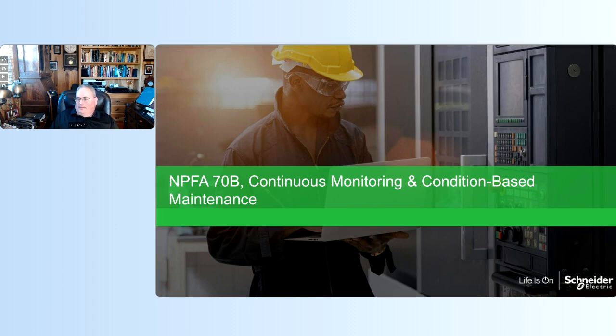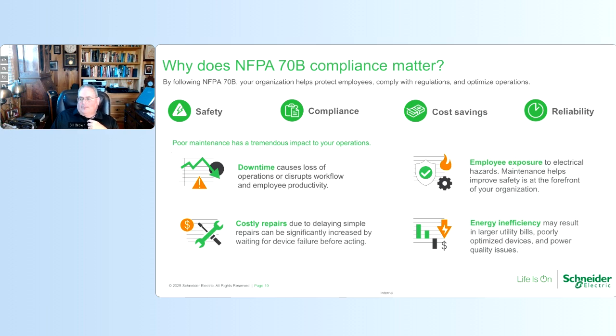So now we're going to talk a little bit about condition-based maintenance in NFPA 70B. So why does NFPA 70B compliance matter? Well, in 2024, NFPA 70B took on the status of an NFPA standard as opposed to a guide. And it can be used by OSHA in citations. While it isn't adopted by governmental jurisdictions the way the National Electrical Code is, it is the consensus standard for maintenance in the United States. By following it, downtime, exposure to hazards, costly repairs due to delayed maintenance, and suboptimal equipment efficiency can be avoided.